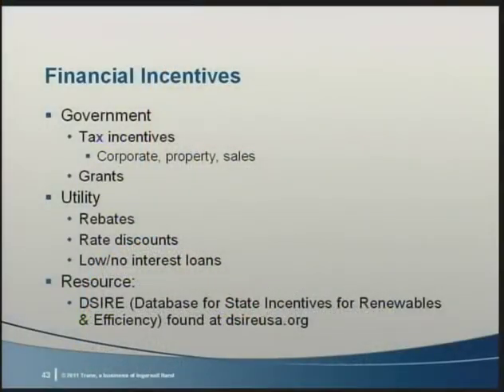Now I want to point out that there are many government and utility incentives out there ranging from rebates to low to no interest loans. These vary greatly by state and utility. As energy demand increases, utilities are being very creative in helping businesses find ways to finance energy efficiency improvement projects and reduce energy consumption. Savings of 10 to 30 cents per kW is common. Rebates for VSDs are often tied to the drive horsepower. For example, $80 per horsepower in California. These can significantly reduce the payback period.